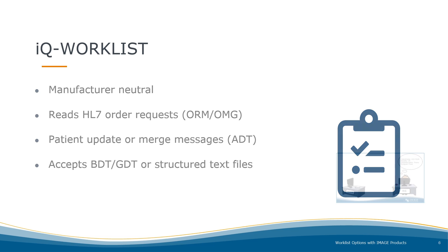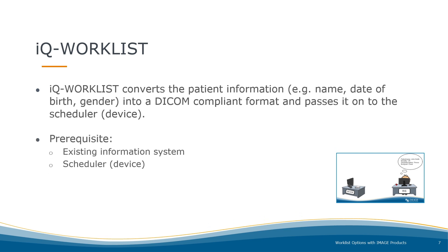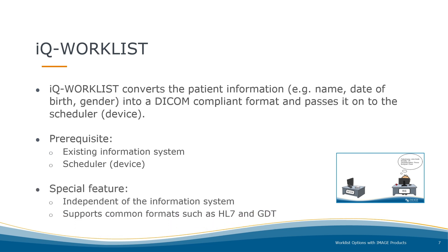What does that mean? IQ Worklist converts patient information into a DICOM-compliant format and passes it on to the device. For this workflow, it is assumed that the information system is able to create a worklist order. What makes IQ Worklist so unique? It is independent of the information system's manufacturer, which means it can be connected to any existing information system. Secondly, it supports commonly used formats like HL7 and GDT.